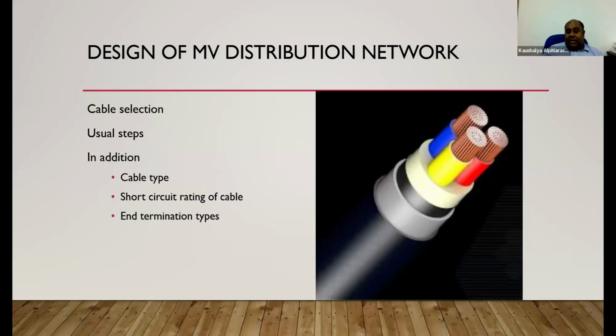But what about the short circuit rating? That has to be calculated and seen. In a 70 millimeter squared cable, you may have somewhere around 6 kA of a short circuit rating for 1 second. If your system needs much more requirement in short circuit capacity, even though you selected those internal arc systems and switchgear rated for 20 kA 1 second or 20 kA 3 seconds or 25 kA 3 seconds, you have compromised your design at your cable end. So calculating the short circuit rating is a must for the cable selection.